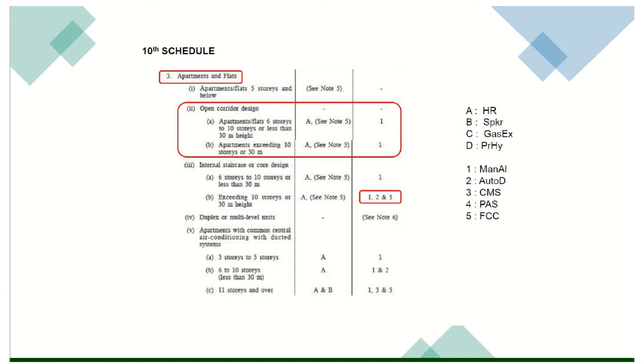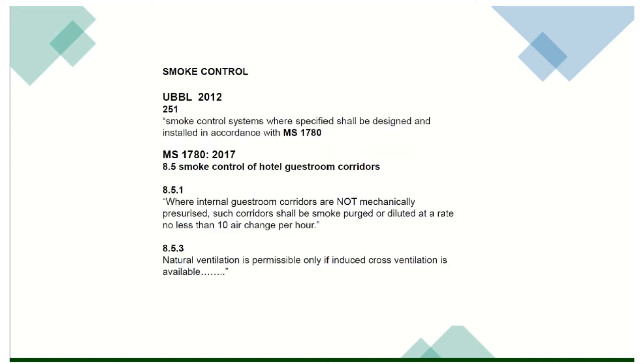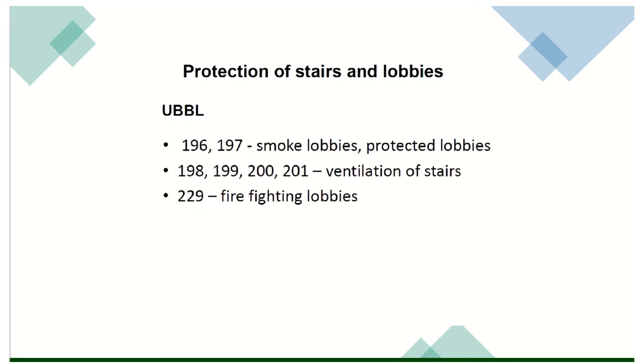Apartment — open corridor. Smoke control system where specified shall be designed and installed in accordance with Malaysian Standard 1780:2017. Smoke control of guestroom corridor where internal guestroom corridors are not mechanically pressurized — such corridor shall be smoke purged or diluted at a rate no less than 10 air changes per hour. Natural ventilation is permissible only if induced cross ventilation is available. Natural ventilation tu sangat penting.